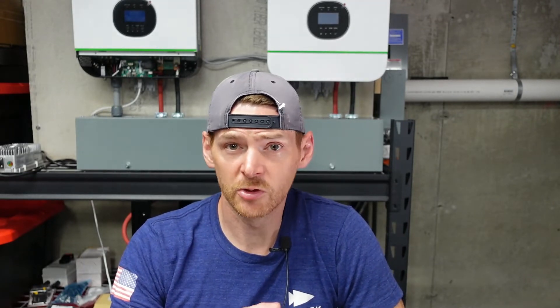Hey guys, this is a quick follow-up video to a couple of videos I posted previously around breaking the ground neutral bonds in a Growatt inverter. The how is pretty straightforward — you open up the cabinet, you remove a couple of screws, and there you go — that ground neutral bond is broken. But I got some questions around why. Why would you actually want to go and do that? So I figured I'd just give you a quick explanation and description of my setup, and hopefully it will make sense as to why I did that.